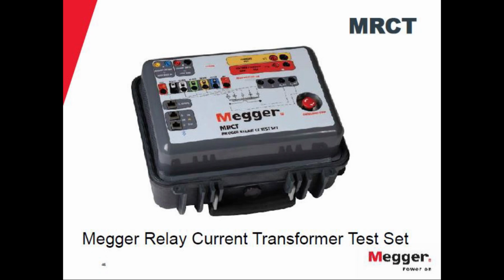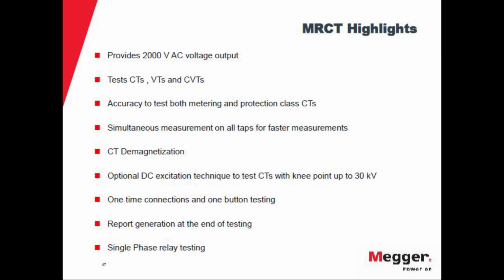So for all of these tests, we have an instrument that can perform all of them with one single instrument. And depending on the CT, sometimes you will have a multi-tap CT. So all of these tests, you will need to do on all of the taps. So that is also increasing the time that you spend testing. With this instrument, you can connect all of the taps and perform the test concurrently in all of them. So it takes like 10 to 15 minutes to run the test in the CT, which previously was taking an hour or probably more with separate instruments.